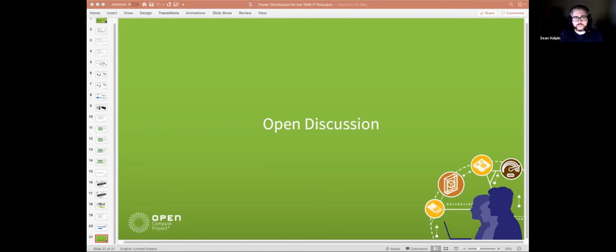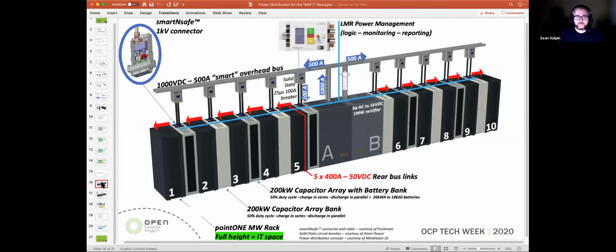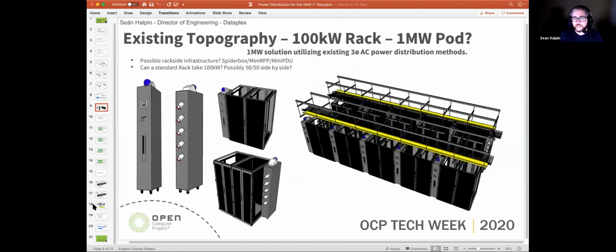The big challenge is on a DC system: how do you simulate the load? Right now a DC load bank in the tens of kilowatts is a scientific unit that can cost tens of thousands of dollars, which isn't really feasible. But if you think about it, you could take a standard AC heater, keep the same elements since they'll still work on DC but just burn hotter, change the AC motor for a DC motor, and change the AC circuitry for a DC power distribution board. You could theoretically come up with a DC load bank reasonably easily, but it would all be new.